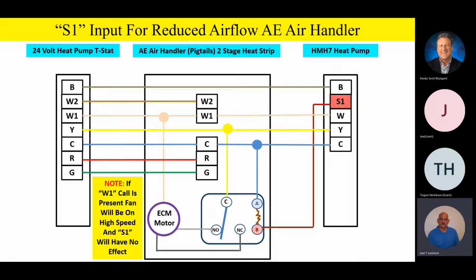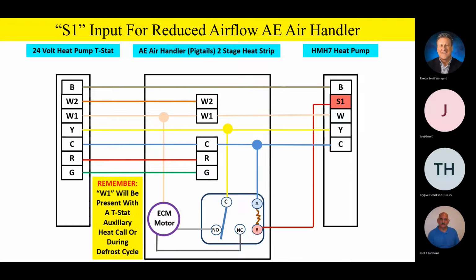So during defrost, even if you have an S1 call on the relay for reduced airflow, if you get an auxiliary heat call or a defrost call, even in reduced capacity, if you get a W1 call, it's going to drive that fan to high speed and basically ignore that S1 reduced airflow signal. And please, one more time, remember that W1 will be present with the thermostat auxiliary heat call or during the defrost cycle.